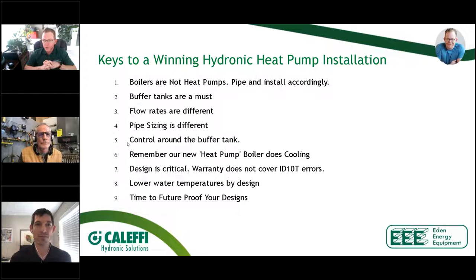The other thing that we've got to talk about, which should be intuitive, is that there has been some feedback that air to waters are a little bit more money than boilers, so we don't know if they're going to get adopted. There's a big difference between an air to water and a boiler in that the boiler only does heating and air to water does heating and cooling. We do have to say that because it does get overlooked that people don't understand you're doing both in one. It also helps us from a design standpoint because in the past we've had to do boilers and then do VRF or standalone air handlers with cooling. We now have a complete packaged unit that you as a hydronics installer designer can now achieve the goals you need to. The other thing that comes into play here, and again, Max is going to talk about this, is design is absolutely critical. Hydronic heat pumps are not something where you go to a job site with 15 different boxes and then kind of figure out how it all goes together.